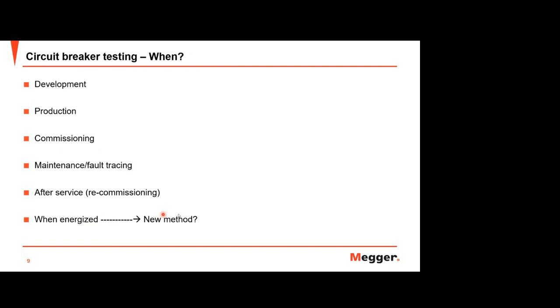So is this a new method? Yeah, actually it is now trending to test your circuit breaker, especially while the system is still energized. So we need some method for testing in this condition. And for example, first trip is one example that can be used to test your circuit breaker while the system is still running.